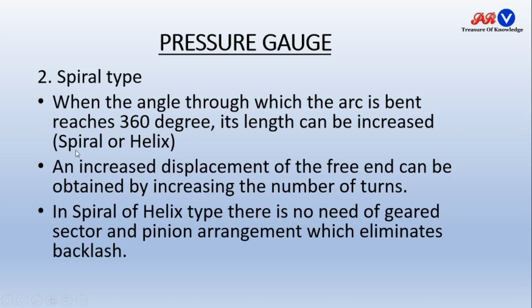The number of turns can be increased in spiral or helix tubes. When we increase the number of turns, we get spiral or helix tubes. In the case of the spiral tube, we have 360-degree rotation of the tube. Its length can be increased to spiral or helix, and increased displacement of the free end can be obtained by increasing the number of turns. As I told, there is no need of amplification of the displacement, because the number of turns will increase the displacement. Also, in spiral or helix type, there is no need of the geared sector and pinion arrangement, which eliminates backlash. These arrangements also produce some hindrance, and this is eliminated by using spiral or helix tubes.